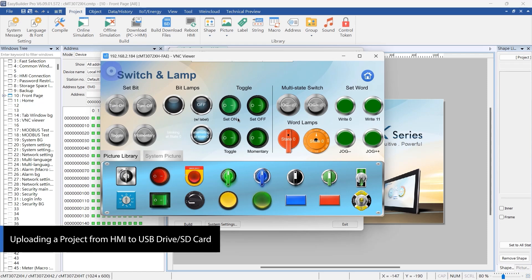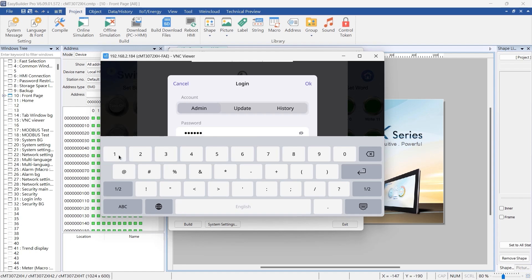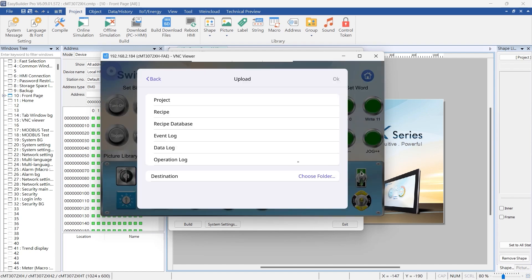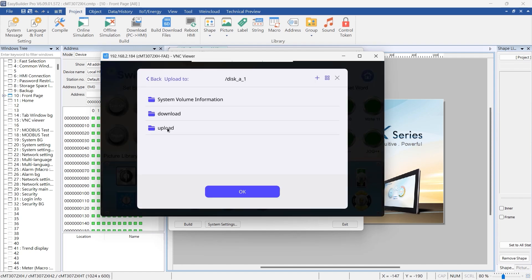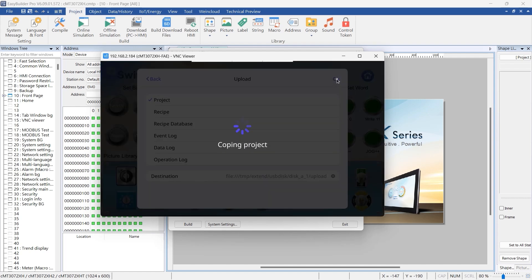Now, insert a USB drive or an SD card into the available slot on your HMI device again. Select the Upload option on your HMI screen to proceed. You will be prompted to enter the upload password. This security measure prevents unauthorized access to your project files. Enter the correct password and continue. After entering the password, select where to save the project file on your USB drive or SD card. Browse to the desired directory and confirm your selection.